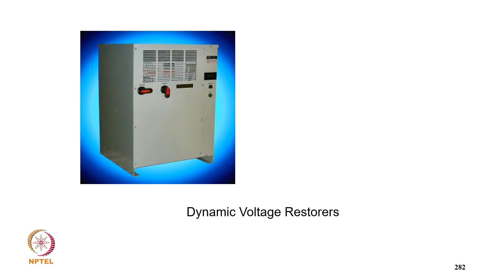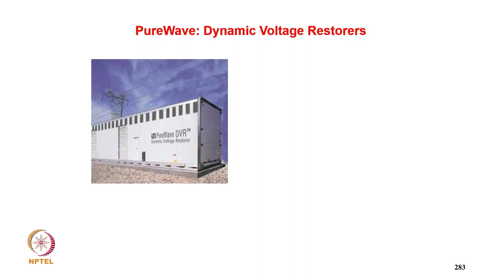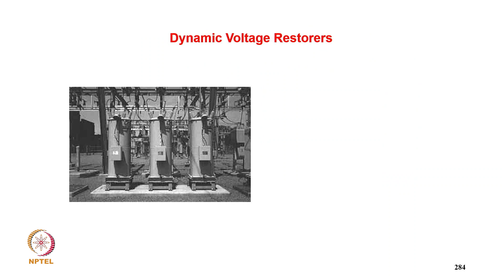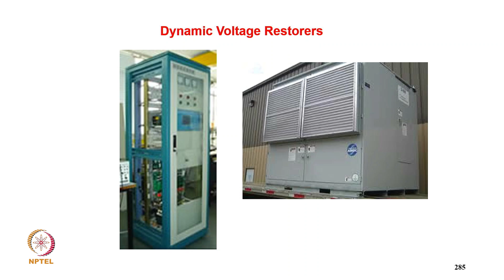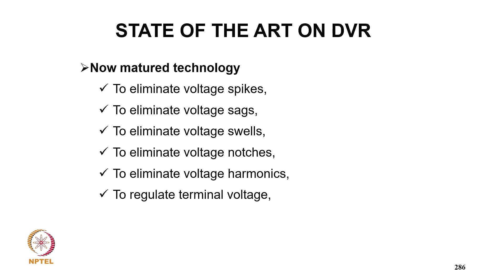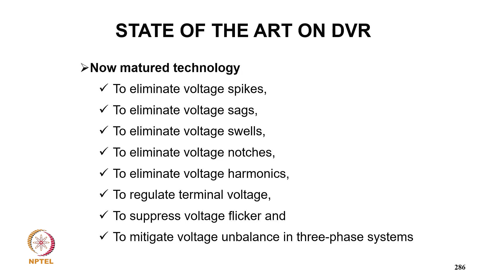Now this is a dynamic voltage restorer made by industry, and a pure sine wave dynamic voltage restorer installed in the field. Then we see how dynamic voltage restorers are installed at different places. It is now a mature technology as far as the DVR is concerned. It is used to eliminate voltage spikes, voltage sag, voltage swell, voltage notches, and voltage harmonics, to regulate the terminal voltage, to suppress voltage flicker, and to mitigate voltage unbalance in a three-phase system.